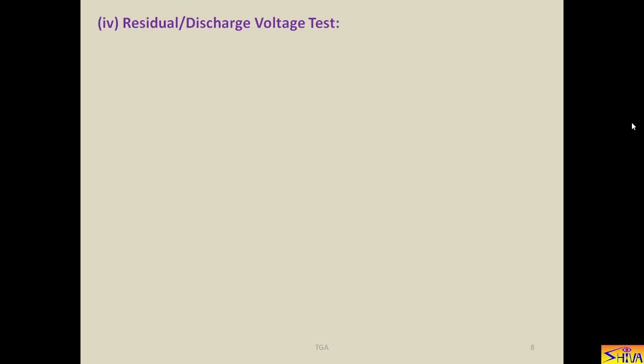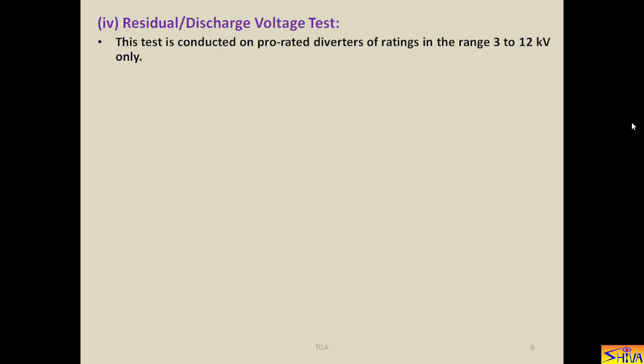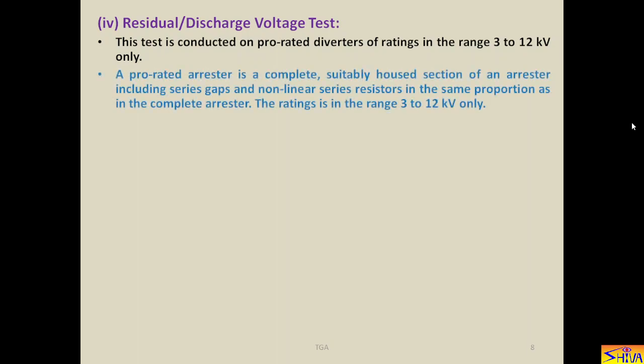Then the residual or discharge voltage test. This test is conducted on prorated diverters of ratings in the range 3 to 12 kV only. Now see what is a prorated lightning arrestor or prorated diverter. A prorated arrestor is a complete suitably housed section of an arrestor including series gaps and non-linear series resistors in the same proportion as in the complete arrestor. The rating is in the range of 3 to 12 kV only.